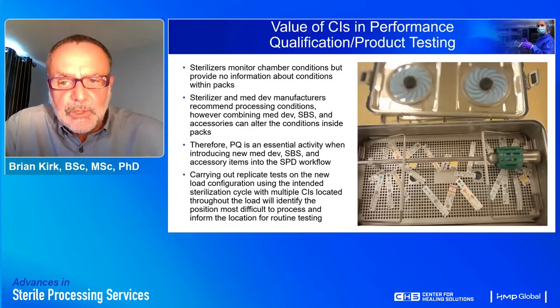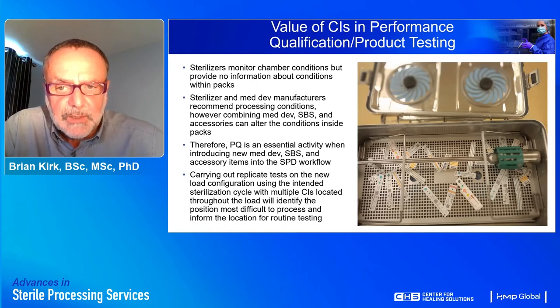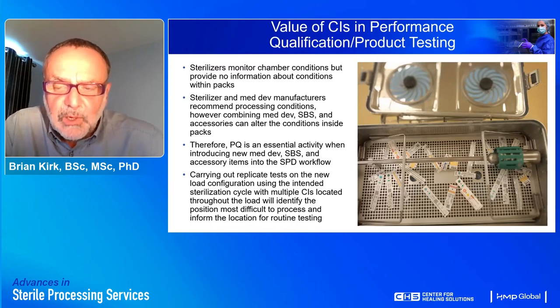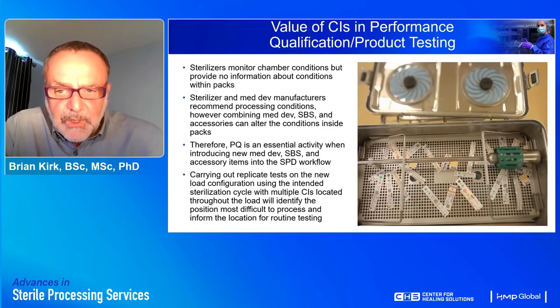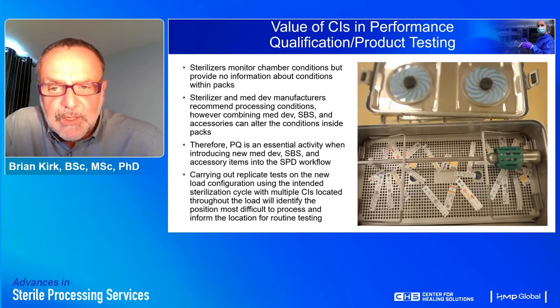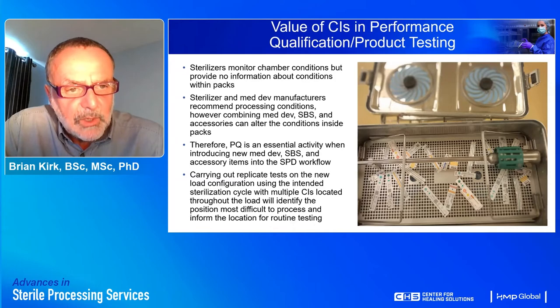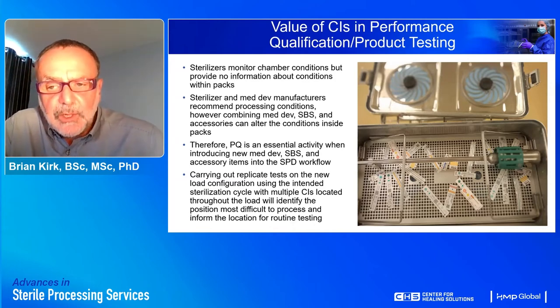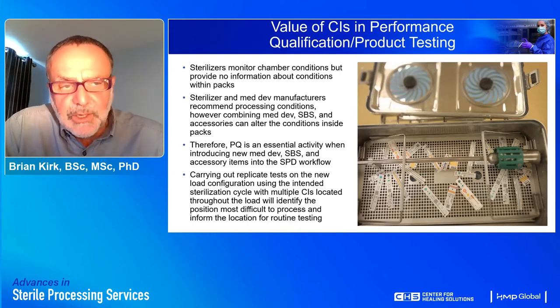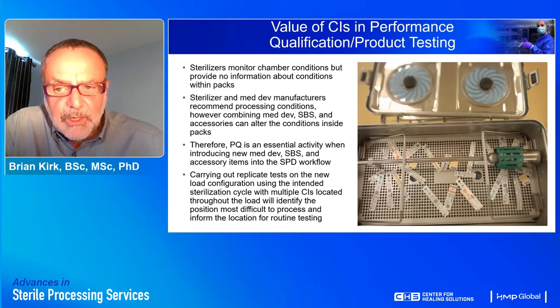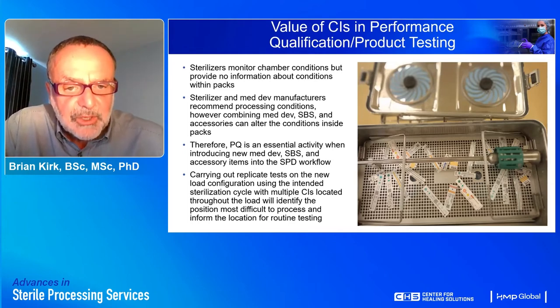Conclusions: sterilizers monitor chamber conditions but provide no information about conditions inside packs. Sterilizer and medical device manufacturers recommend processing conditions; however, combining the medical device, sterile barrier system, and accessories can alter the conditions inside packs. It is therefore essential that performance qualification is undertaken when introducing a new medical device, sterile barrier system, or accessory into the SPD workflow, running replicate tests on the new load configuration using the intended sterilization cycle with multiple CIs located throughout the load to identify the best position to place them.